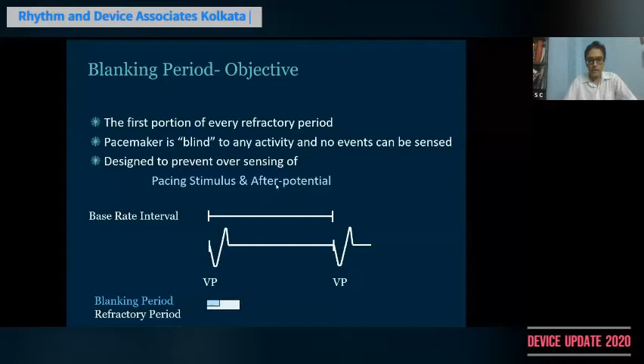Okay. So this is a blanking period, which actually takes care of your afterpotentials or any events occurring at the beginning of your refractory period, which is not stored by the pacemaker, not sensed, basically ignored by the pacemaker. So other than these two periods, there is a new period which is left, which comes after the refractory period to the next event. This new period is called an alert period.